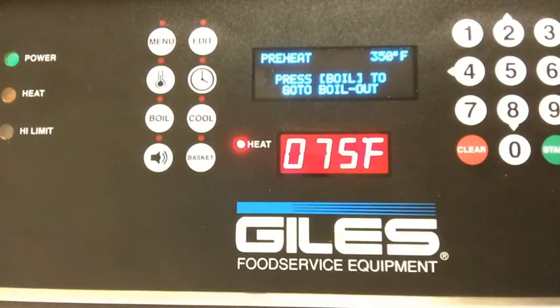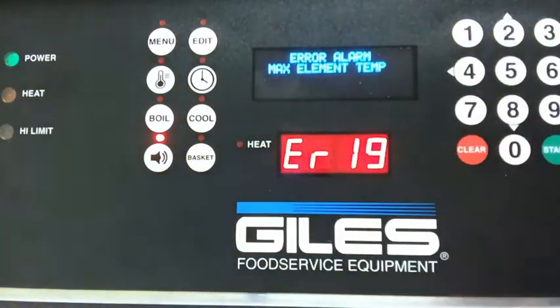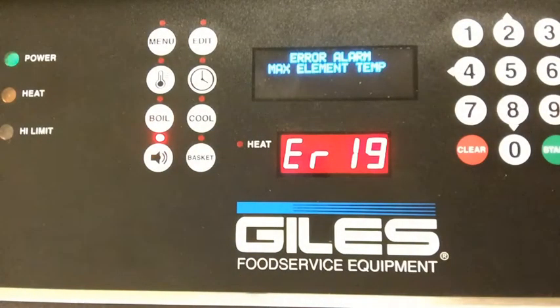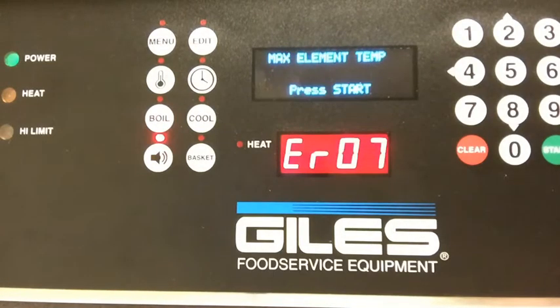Now if we had the unit running and the oil got below the element, that element sensor would definitely cause it to go into alarm. When it does, it will display on here, error alarm, max element temperature. It's exceeded that max element temperature setting that we established back during our user settings. So we're going to get an ER19. Now, if for whatever reason it cools back down, it will allow it to reset by pressing start.